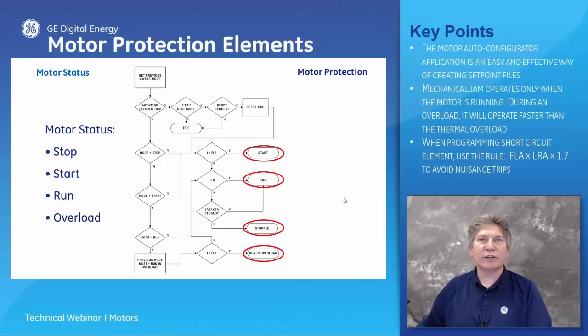As well, the learned values such as the learned starting thermal capacity, learned starting current, and learned acceleration time can be inaccurately calculated. This type of problem can occur when a synchronous motor with a fixed field is run at no load. To overcome this problem, a digital input should be configured to read the status of the breaker and determine whether the motor is stopped or simply idling. With the spare input configured as starter status and the breaker auxiliary contacts wired across the spare input terminals, the relay senses a stopped motor condition only when the phase current is below 5% of CT and the breaker is open. If both of these conditions are not met, the relay will continue to operate as if the motor is running and the starting elements remain unchanged.